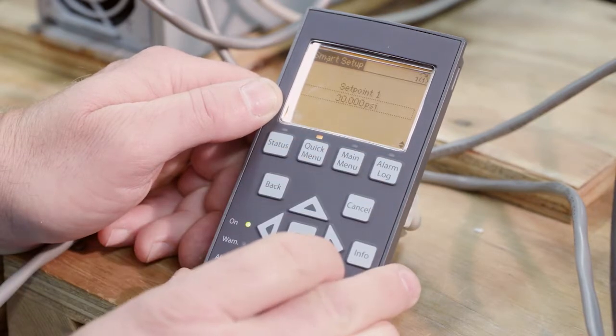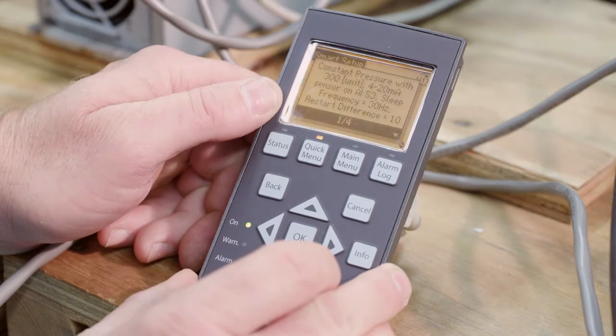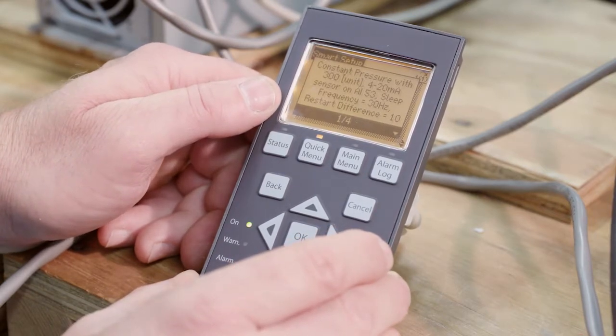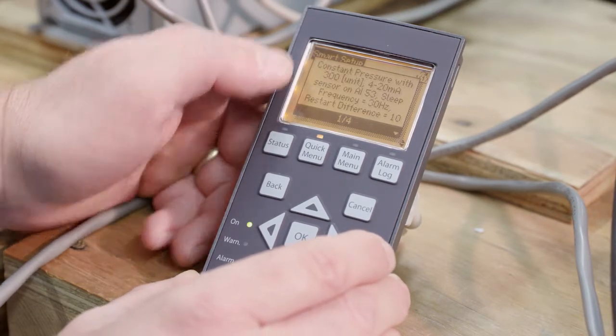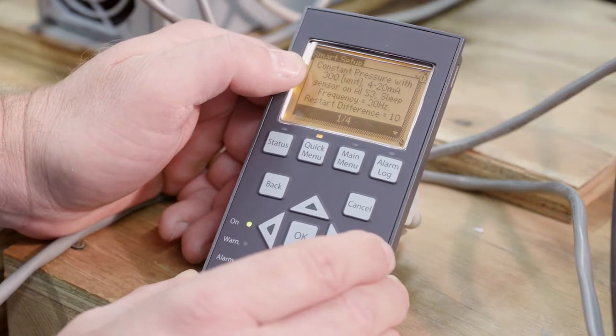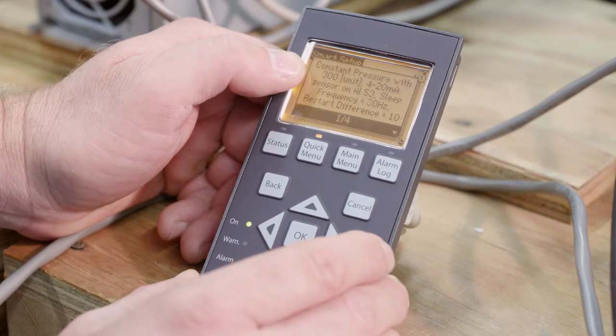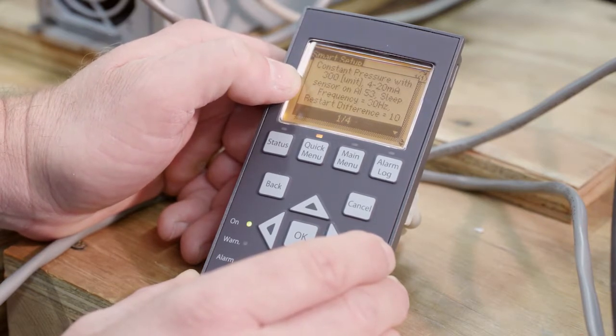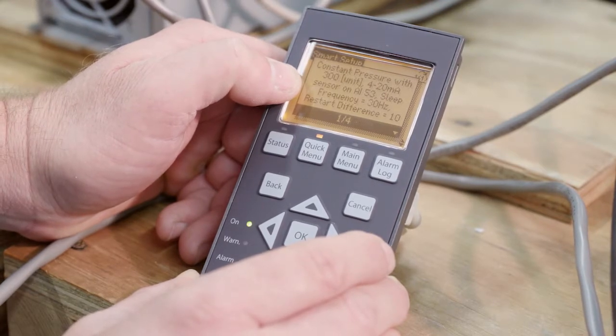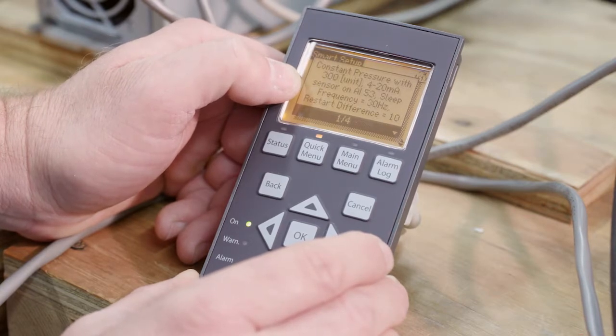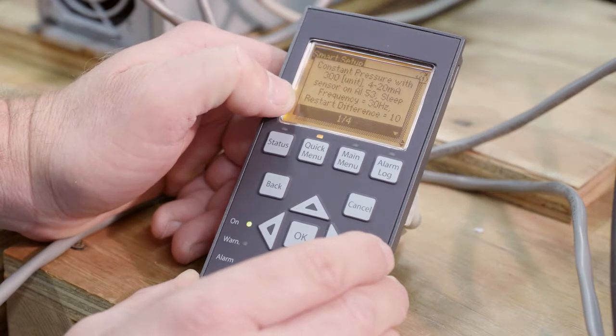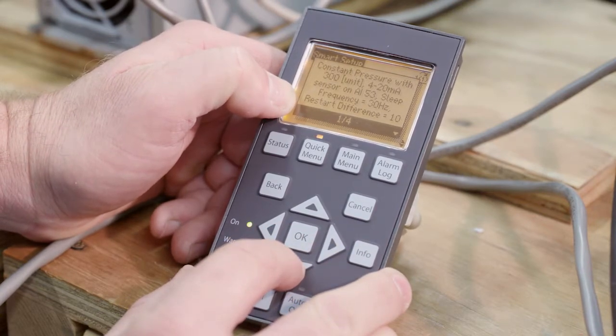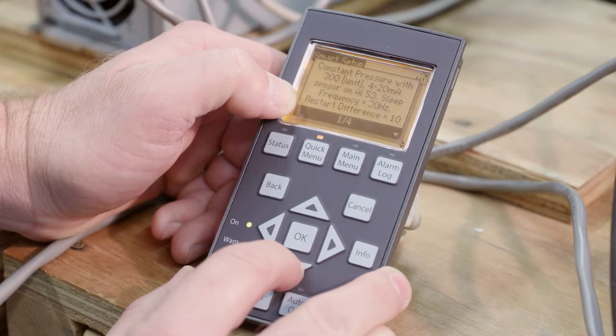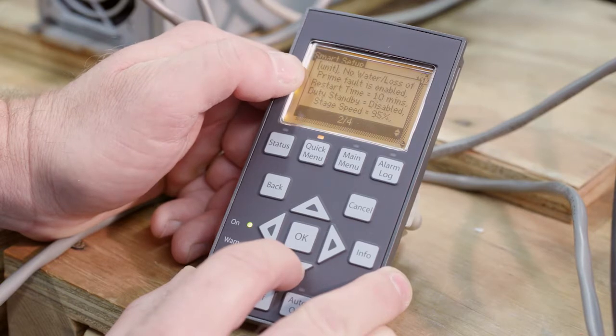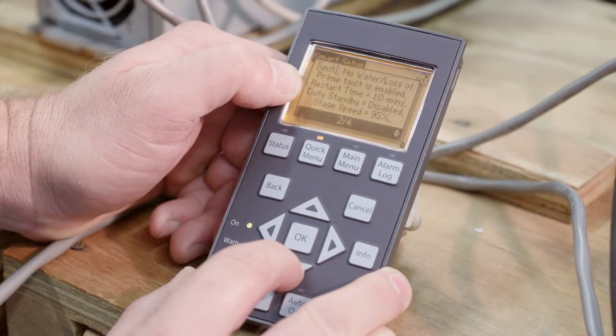And again, remember, anytime you make a change, you got to hit the down arrow to save it. So this is important because it's reminding you, you hit auto set. And this is everything that's set in the background. Constant pressure with a 300 unit or PSI transducer, which is what we have. 4 to 20 milliamp sensor, which is what we have. It's on AI53 or analog input 53, which we showed earlier. The white wire is on 53. Sleep frequency is 30 hertz. Restart difference is 10. Okay, when do you want it to wake back up again? And defaults to 10, and that's in PSI, so that's 10 PSI below your set point.